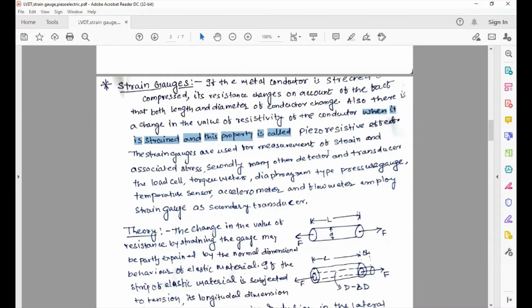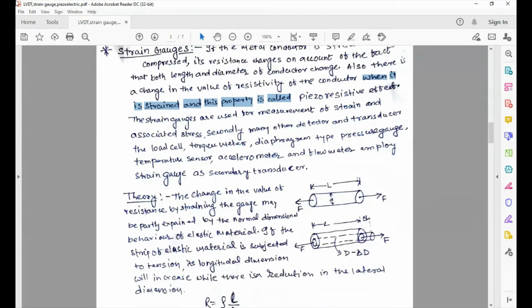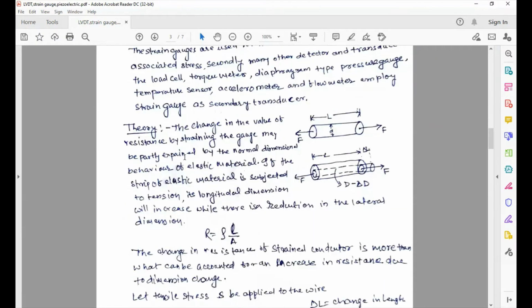Strain gauge is used for measurement of strain and associated stress. Many other detectors or transducers use strain gauge as a secondary transducer, such as load cell, torque meter, diaphragm type pressure gauge, temperature sensor, accelerometer, and flow meter.